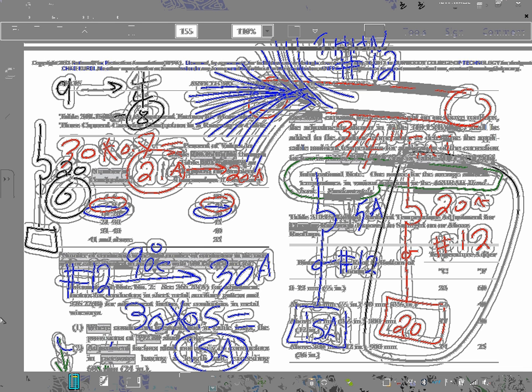Under normal operating condition, the temperature of the conductor, the THHN and TW, is one factor. Then you go to the other rules that say 100 amp or less, number 1 or less, 60 degree column. More than 100, more than number 1, 75 degree column. Motors, 75 degree column. These are your default, unless they tell you otherwise. What do they tell you otherwise? The lugs on both ends of the conductor are rated. Engineers say all lugs must be rated for 75 or higher. That's how we cover our butts. Then we size everything by 75.